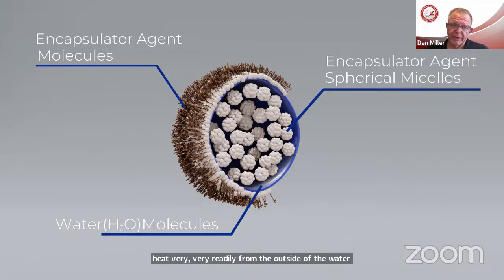Now, the skin of the water droplet is lined with F500 molecules pointing the other way. The polar head is attracted to the water, the nonpolar tail points away from the water, gathering heat and grabbing onto more carbons and hydrocarbons. Together, those things protect the water droplet from extreme heat, help absorb heat into the center, and then the carbons and hydrocarbons are stuck and trapped inside the spherical micelle, or locked up. They're locked away from oxidation, which would allow combustion, so once those carbons and hydrocarbons are trapped in there, combustion ceases. It's not able to happen anymore.